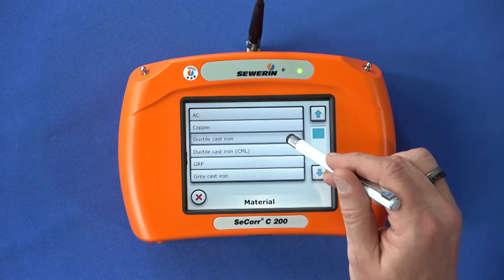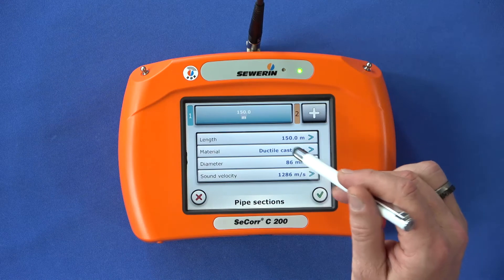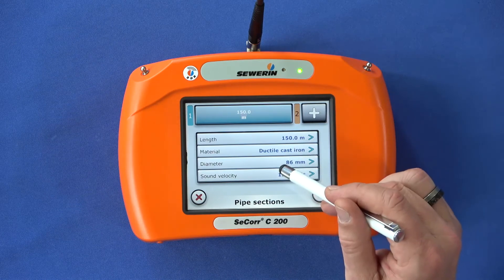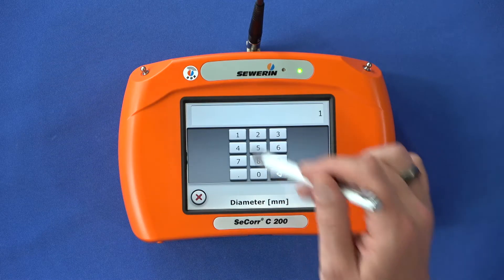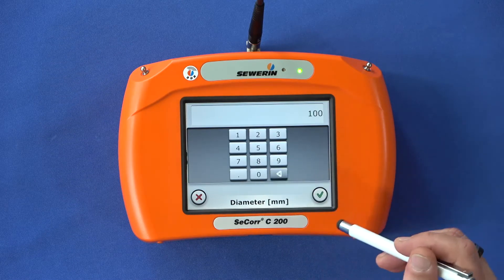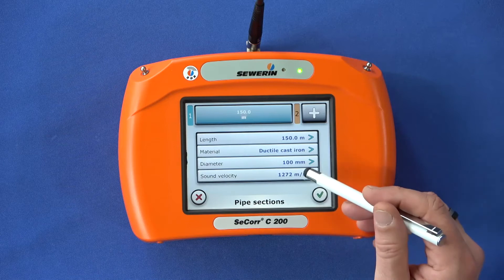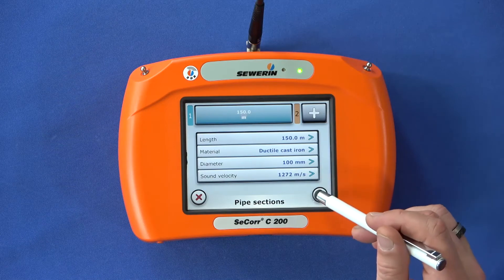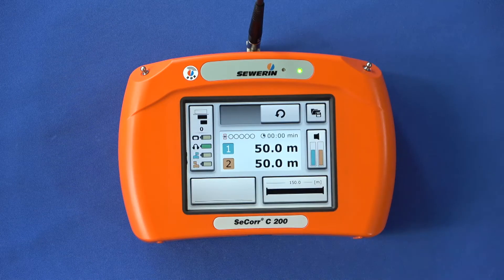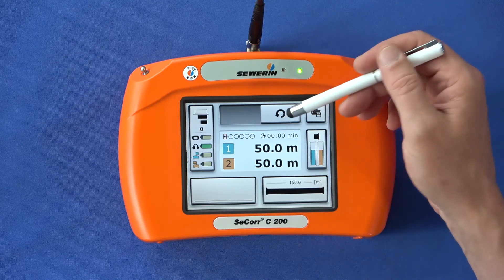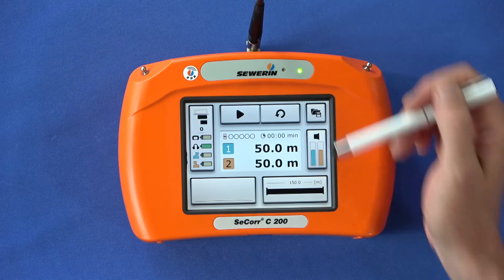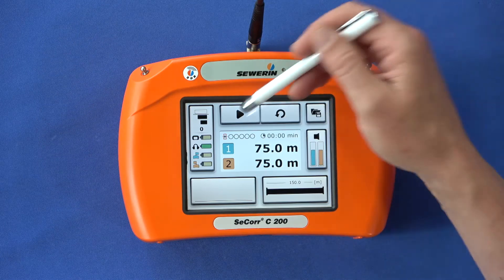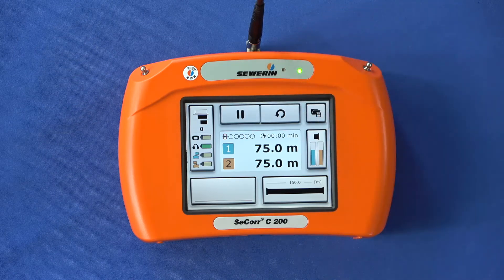Now select the diameter of the line. Please note that this is based on the nominal diameter of the line. Tap on diameter and enter the data. The speed of sound used for this measurement is displayed. Confirm your details with the green check mark and you will return to the measurement screen. You will see the new measurement button above the results field. Tap the button and the measurement is ready to start — the start button appears.